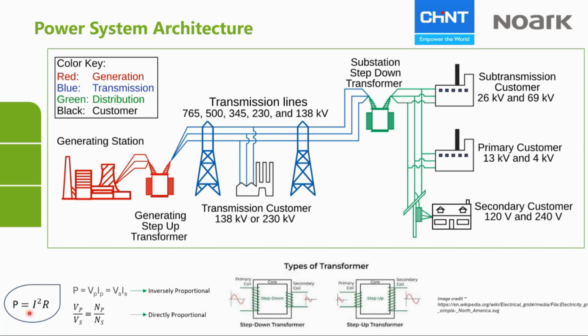And that helps you with an efficient transmission line, because power loss across the transmission line can be significant, especially if, and that's always the case, the generating station is hundreds or thousands of kilometers away from the end customer. So you want to reduce as much loss as possible, because from my elementary physics, power loss is the square of current multiplied by the resistance along the line. So if you have lots of current along that transmission line, you're going to have so much power loss, and that defeats the purpose of your power being generated. So what we do with the step-up transformer is reduce that current to the barest minimum so that the overall loss along the line is reduced significantly.